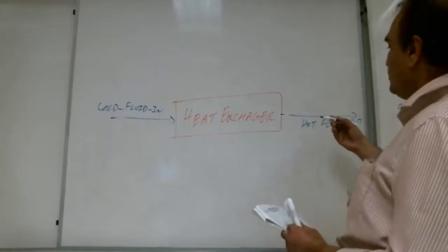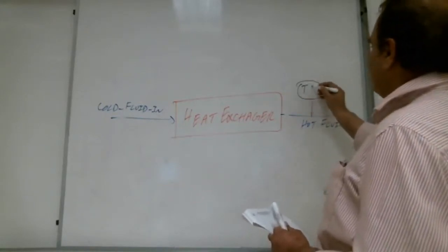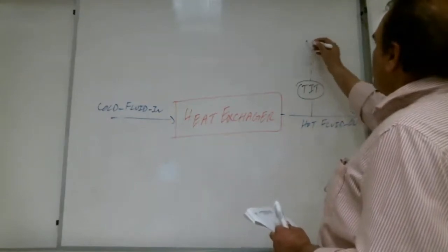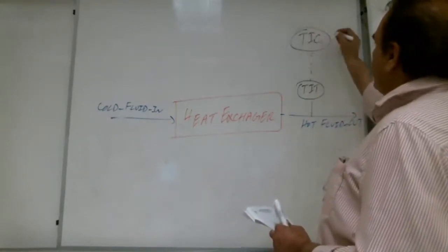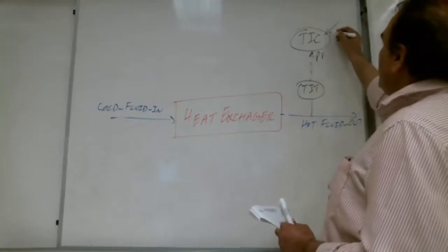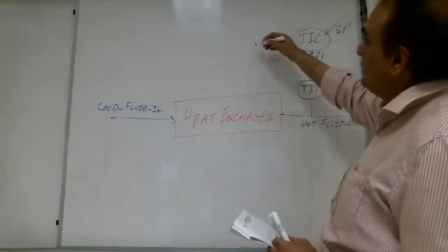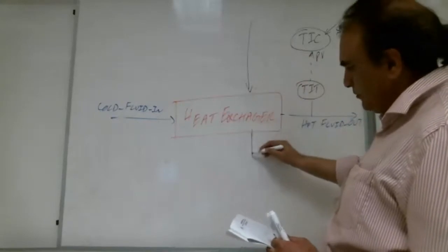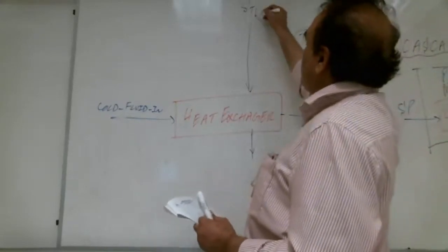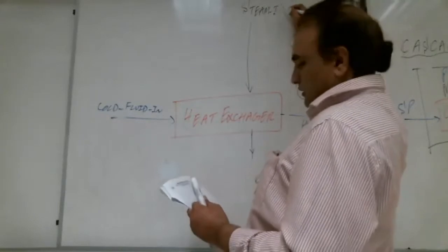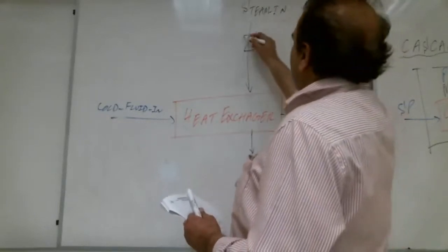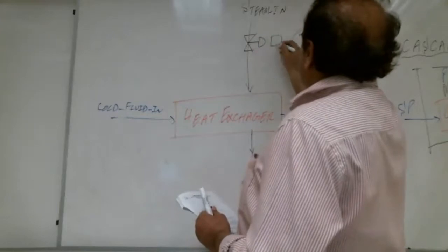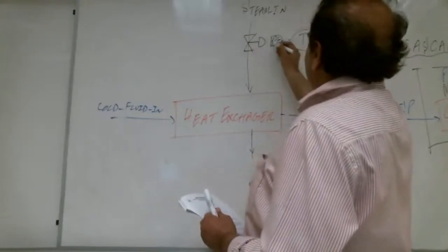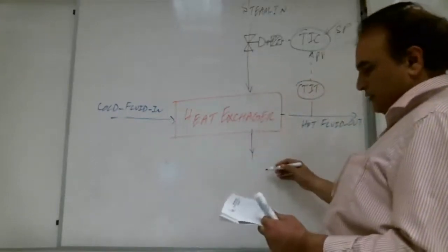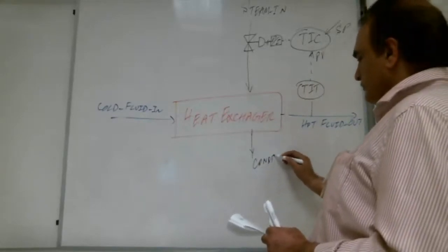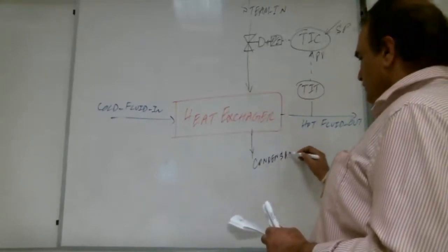Then here we take the temperature indicator transmitter that goes to the temperature indicator controller. This is PV, we all know. This is set point, and this is the steam line. Steam in, and what we do, we put here the valve. I2P converter is there, and this is condensate. Condensate out.